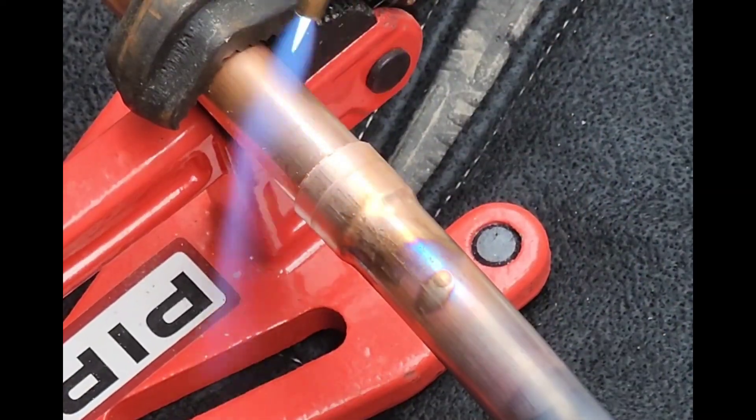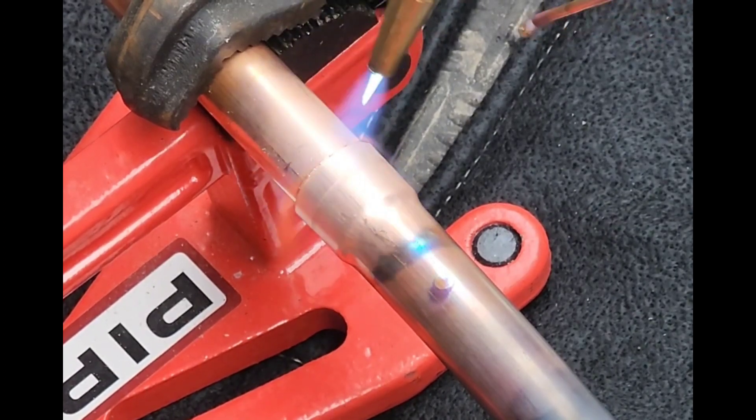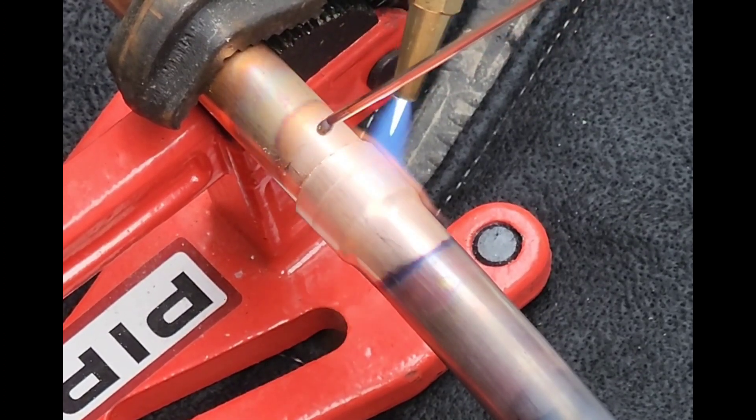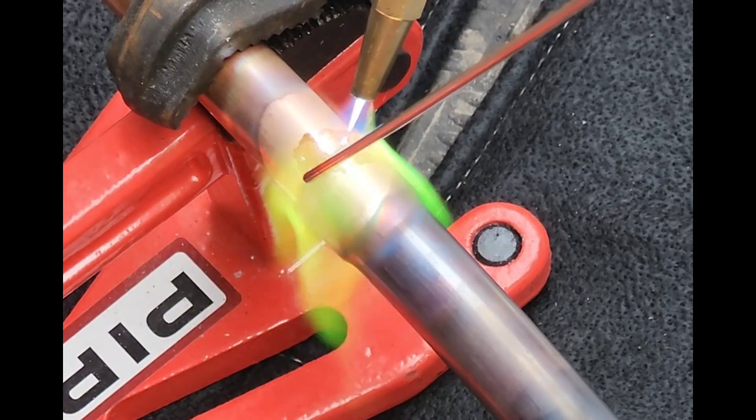Now we're brazing up a joint — that is three-quarter inch copper again, using the same tip and 15% Sil-Fos — and you can see that flame is putting some nice heat into that copper joint, and that 15% Sil-Fos is flowing beautifully.